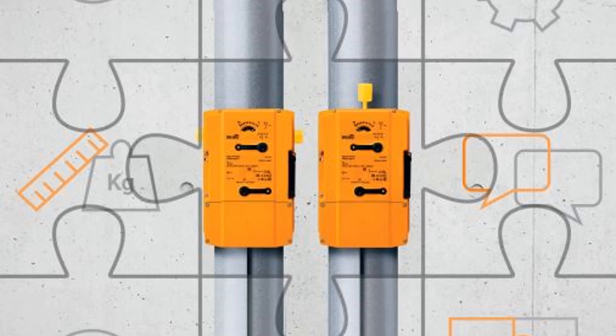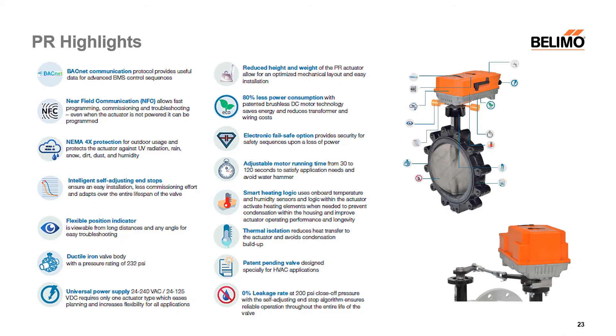Now we move into our PR, our latest and greatest actuator designed specifically for the HVAC market. We took a look at what an actuator would need specifically for a butterfly valve — its weight, height, and electricity usage. We built in a smart heater that turns on only when necessary, variable run times that use much less electricity than competitor actuators, a flexible indicator visible from quite a distance, universal power, and intelligent self-adjusting end stops. As the valve wears, the actuator pushes a little further into the rubber to ensure that 200 PSI close-off is maintained.